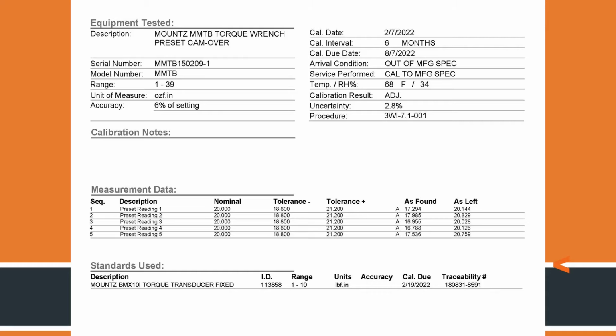Now typically when you get this cert, it's going to tell you which tool you're using, the serial number of that tool, the range of that tool, the unit of measurement that it's being measured in, its accuracy statement. And so for hand tools, anything under 10 Newton meters is going to be at 6%. If you go above that, then it's going to drop down to 4%. And then you're going to have the calibration date when it was done, the interval date, and then the really big item that we need to take a look at is going to be the arrival condition.